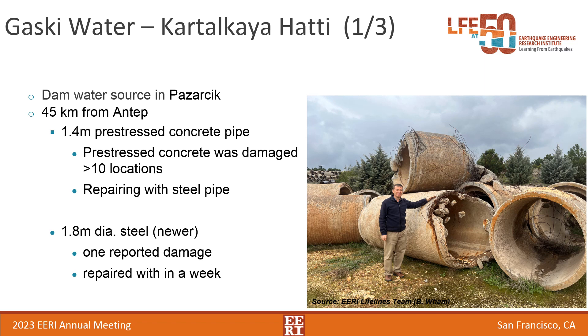This province gets water from three sources. The first is the Kartalkaya transmission line, which is dam-sourced and about 45 kilometers from Antep with two parallel lines. The older 1.4-meter pre-stressed concrete pipe was damaged in 10 locations and required extensive repairs with large sections removed. They had a newer 1.8-meter diameter pipe installed parallel to it, and that was one of the few ways this area was able to bring water in shortly after the earthquake.